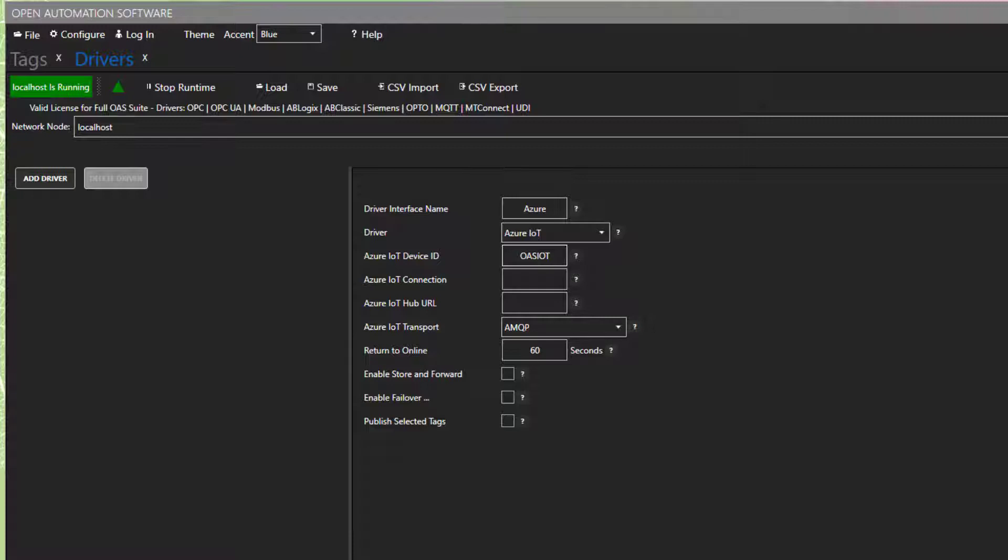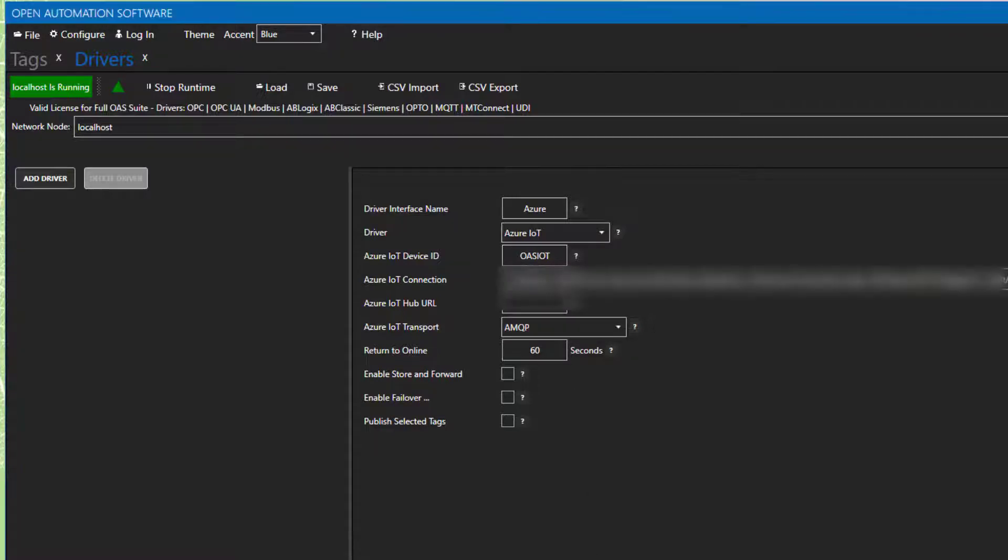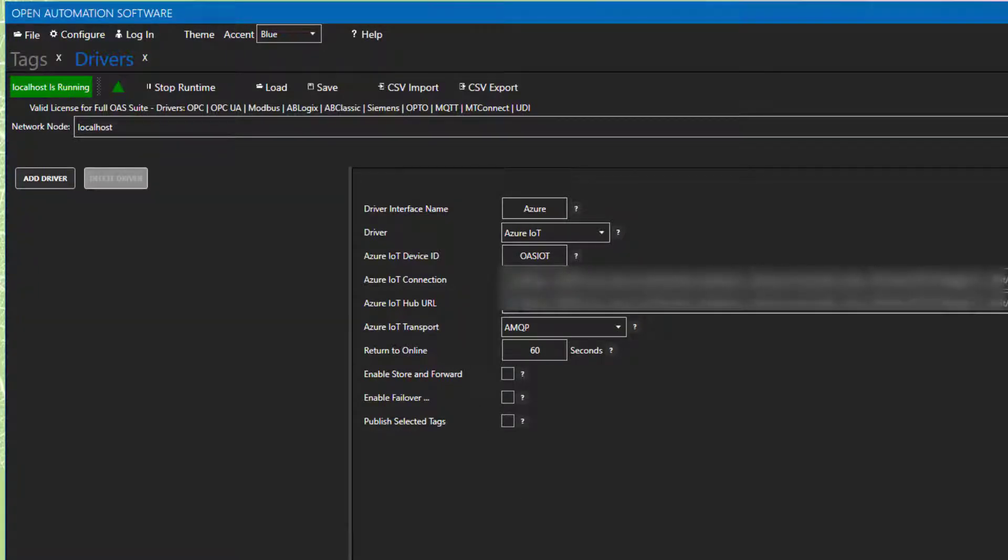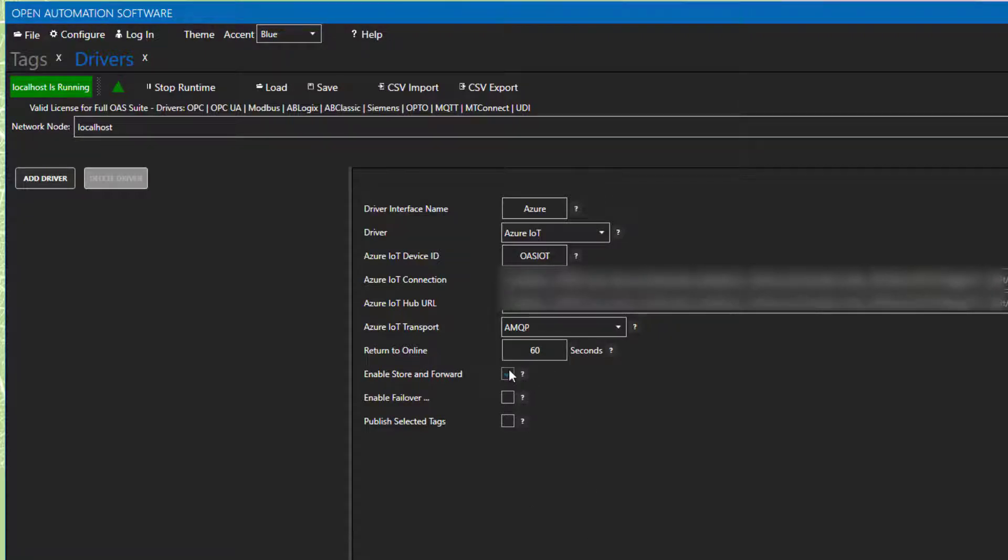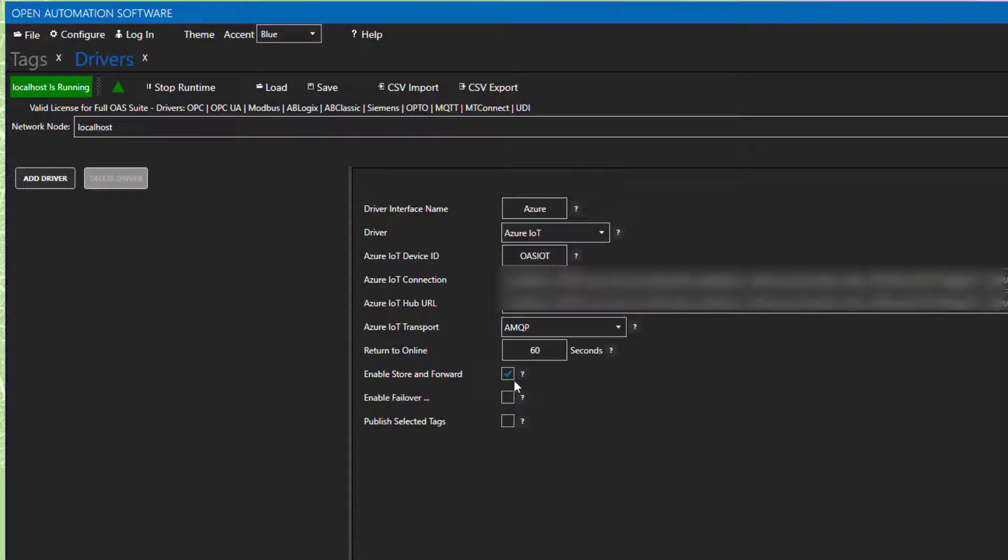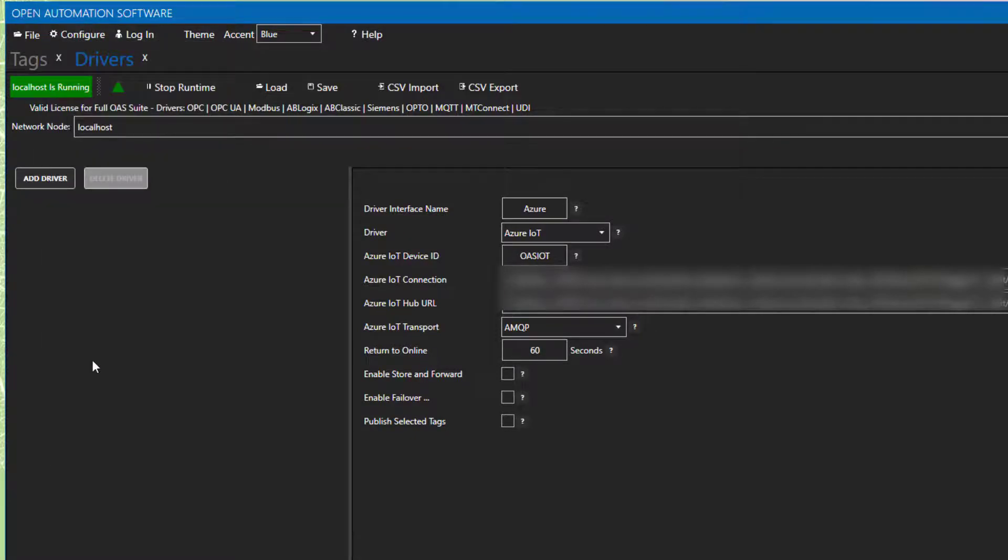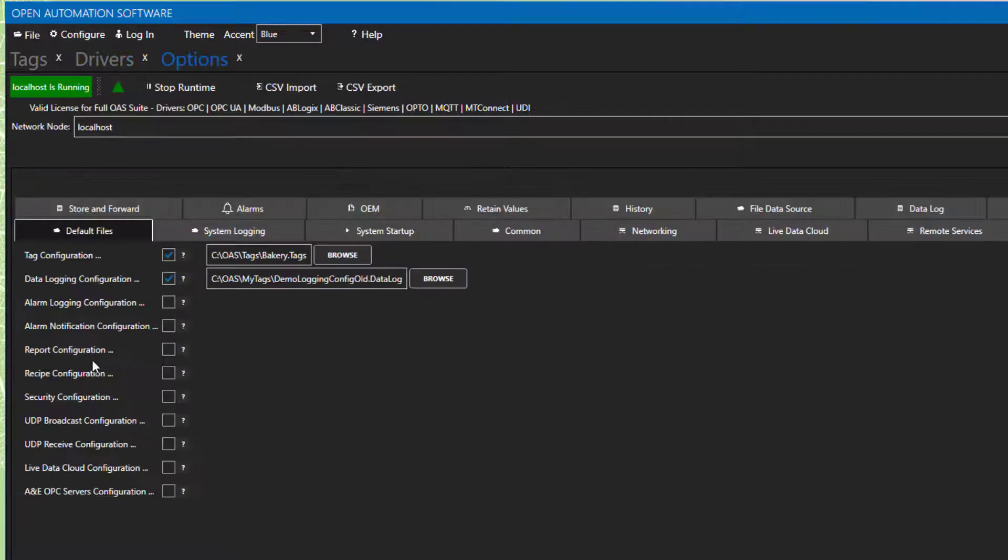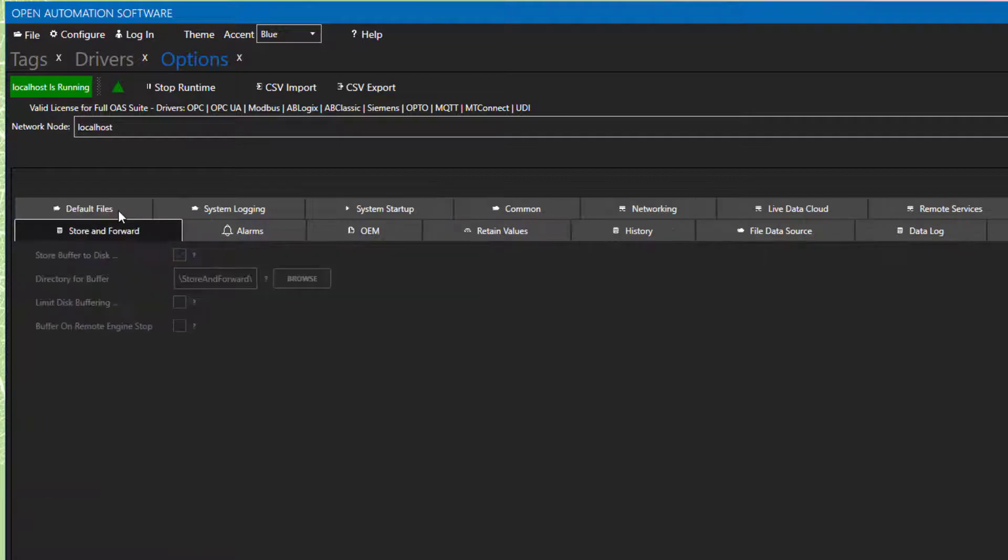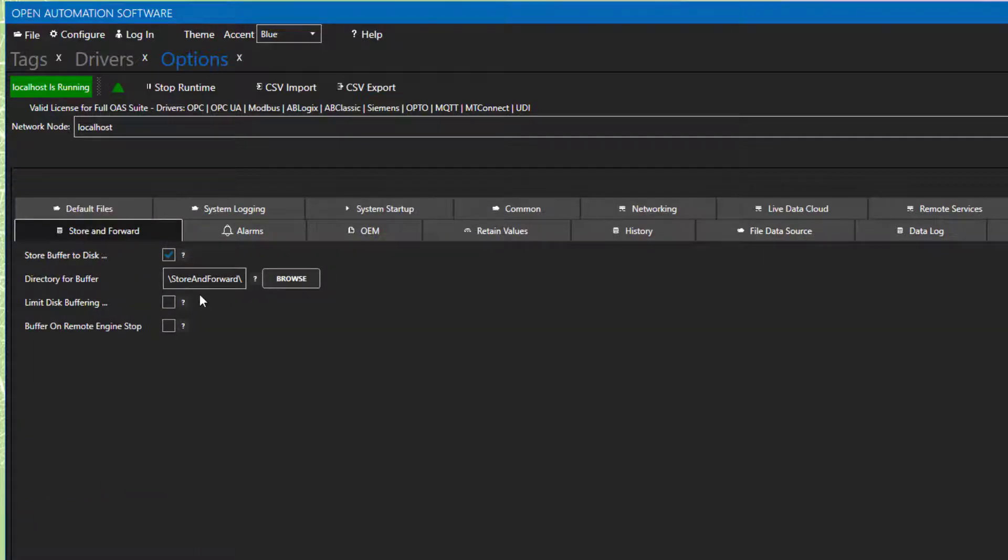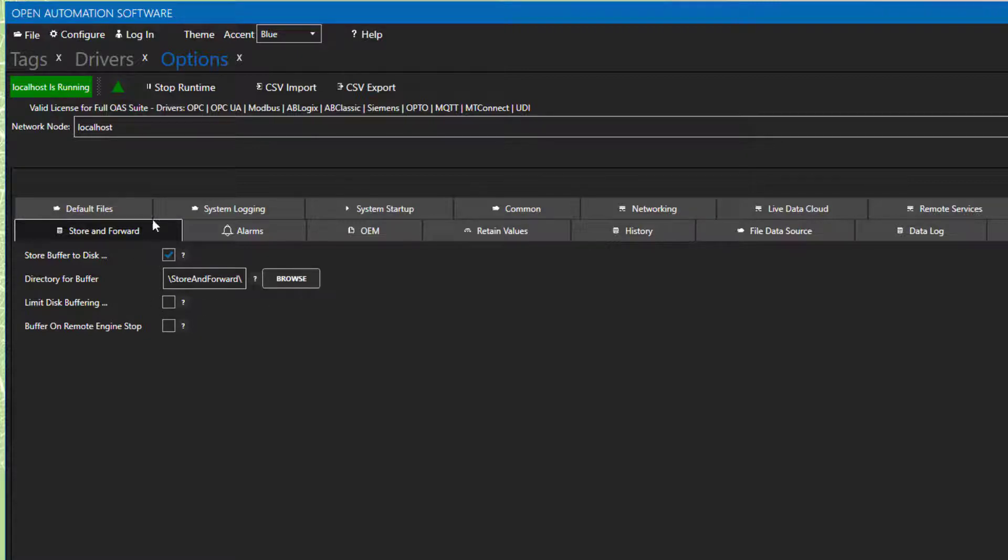I want to point out this checkbox for Enable Store and Forward. If you enable this, it will buffer the data in the case of a communication failure. Then, it will send the data out when the communication is restored. Under the Configure Options menu on the Store and Forward tab, you can choose which directory you would like to store the buffered data. You can also set a limit on the amount of time that data will be buffered. This is a great feature that prevents data loss.